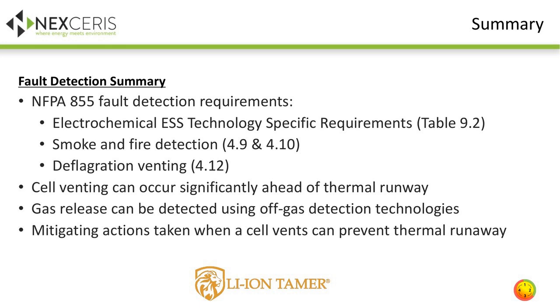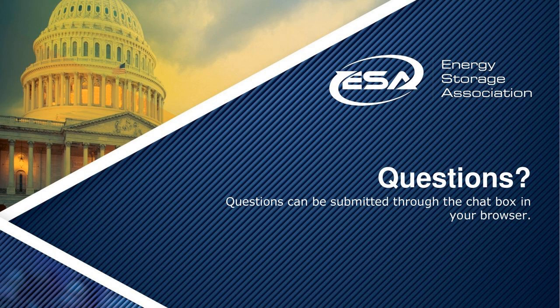So in summary, and I'll try and wrap up here and leave some time for questions, we looked at some of the sections where fault detection currently is. We've also looked at some areas where fault detection can go using the measurement of the cell venting, looking through the case studies of those, and then demonstration that mitigating actions taken when a cell vents actually does provide enough time to help protect against thermal runaway. Which is one of the ways, if we dial back to the initial comments, that you can use this as part of the hazard mitigation analysis that is required within the current 855 standard. It's something that can be used as a supplement and provide an additional layer of protection to your systems. So with that, I'm going to turn it back over to Sonora, and we'll look through some of the questions.